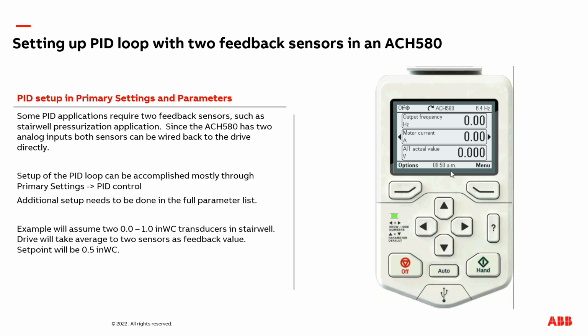Now, one of the cool tricks is on the home screen, obviously we have output frequency, current, and your analog input value and voltage. If you click the left button here, we have a pre-canned PID setup menu. You have your set point on top, that's a 1/2 inch of water column, that's correct. We have our feedback here, and we have our output frequency. Well, if you think about it, we have 2 transducers. So this normally would just represent the one transducer, which would be fine. What are both my transducers at right now?